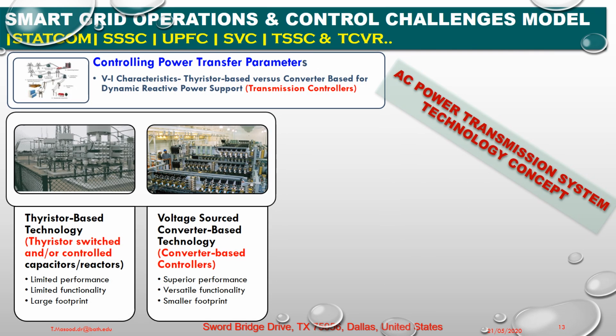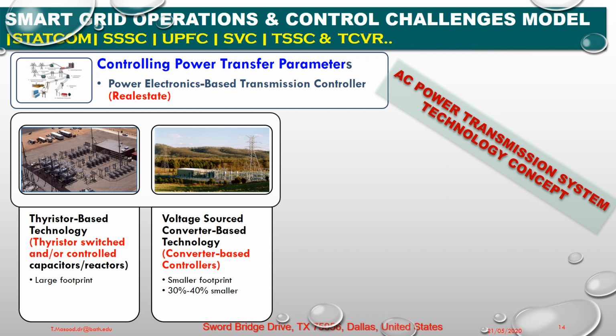Okay, now we have a few highlights on characteristic thyristor base versus what we get again. As we have discussed, the first thyristor based technology, thyristor switch and control capacitor reactor, has limited performance, limited functionality and large footprint. Compared to that, voltage source converter based technology has superior performance, versatile functionality and small footprint. These are the three main key elements which make the difference between the V and I characteristic of the SVC and STATCOM. Second, the thyristor switch has a large footprint, and it's very important here, while this has a smaller footprint, 30 to 40% smaller compared to the SVC.